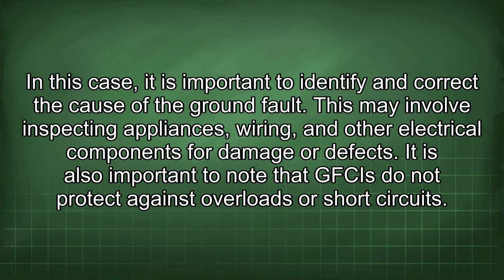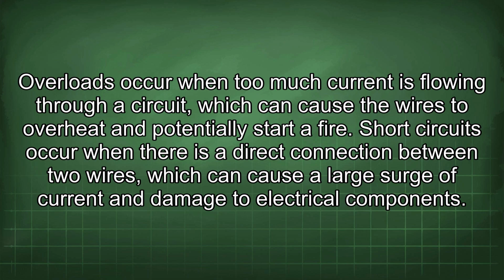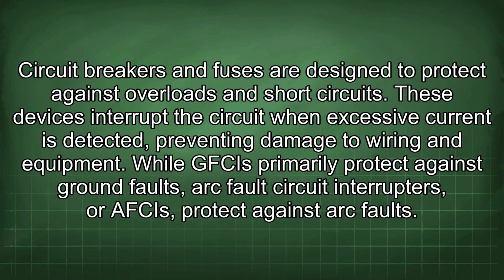It is also important to note that GFCIs do not protect against overloads or short circuits. Overloads occur when too much current is flowing through a circuit, which can cause the wires to overheat and potentially start a fire. Short circuits occur when there is a direct connection between two wires, which can cause a large surge of current and damage to electrical components. Circuit breakers and fuses are designed to protect against overloads and short circuits. These devices interrupt the circuit when excessive current is detected, preventing damage to wiring and equipment.